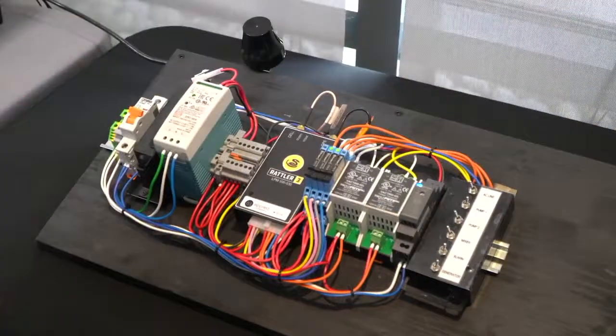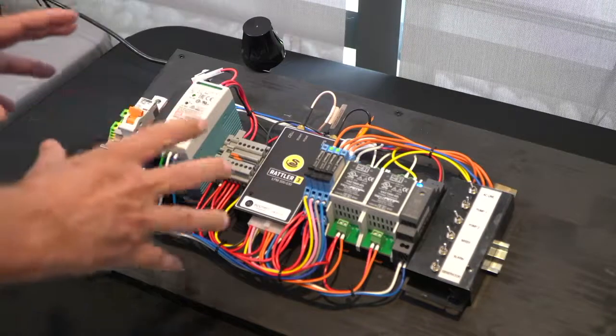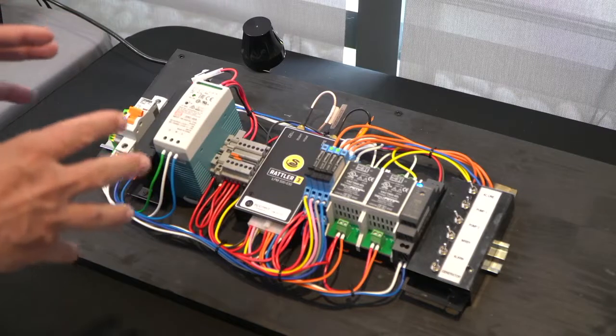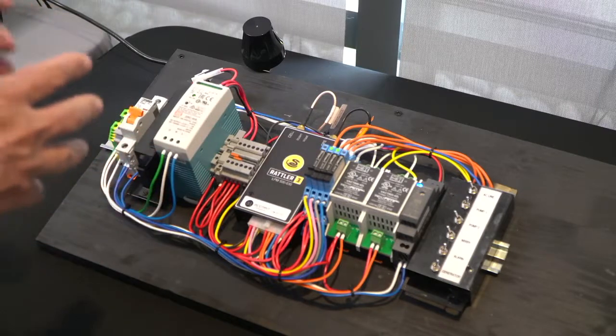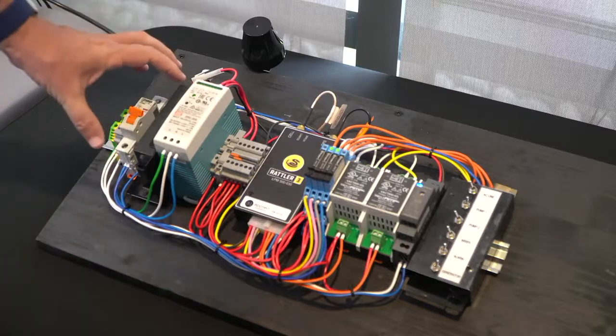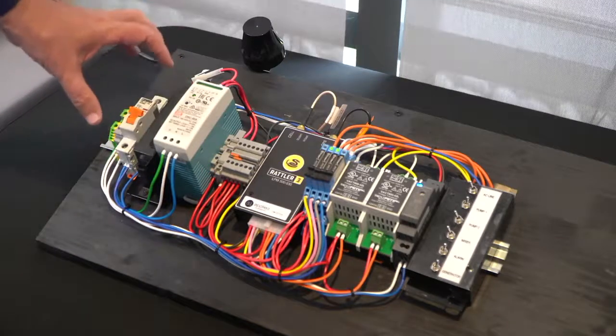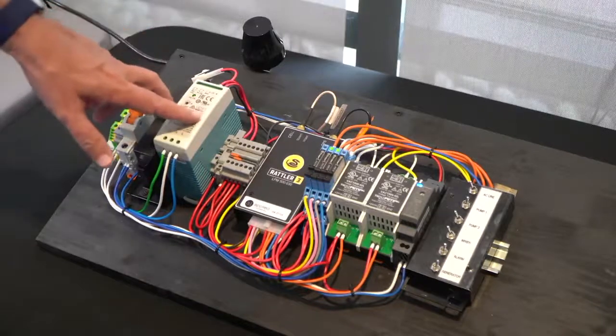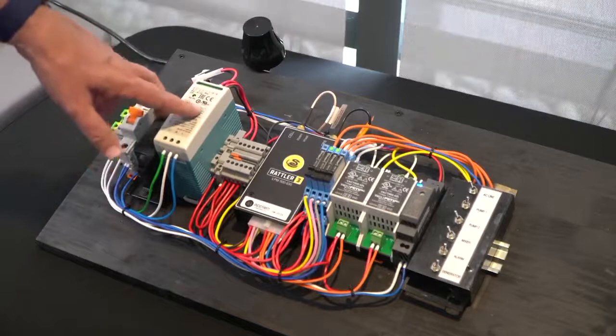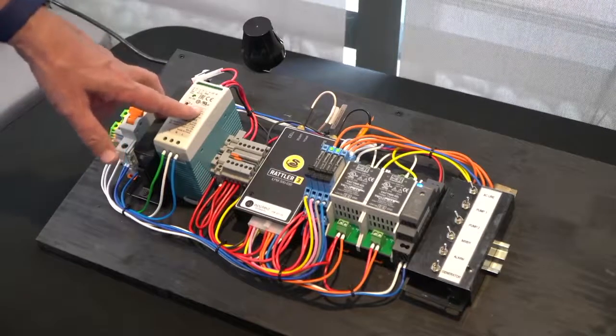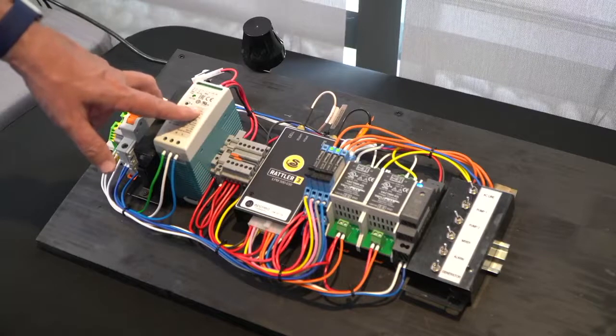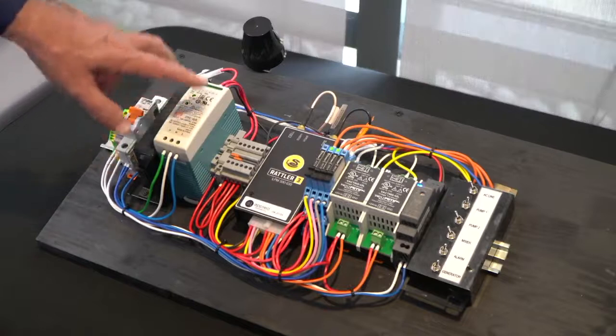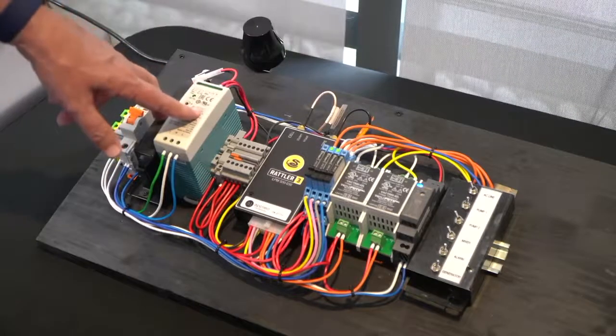What we have here is the typical equipment that's in a small cabinet at a remote lift station. And I'm going to go through each of the elements in turn so that you can see how straightforward it is to manage and monitor and control all the critical elements that make up a lift station. This is an incoming power supply with a line power and a circuit breaker. This over here is what we call the last gasp battery. What it does is it provides battery power in the event of the mains failing so that the Rattler can still communicate with Glance and with the central and report that the AC power has failed. You don't need to have somebody go out and check it, because this battery will keep the system up to be able to report it.